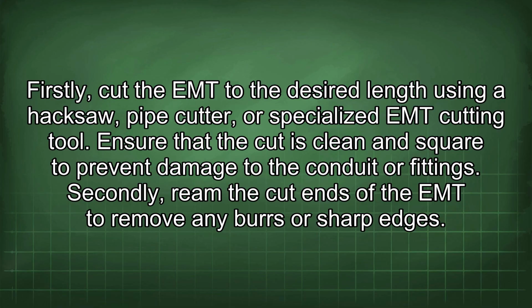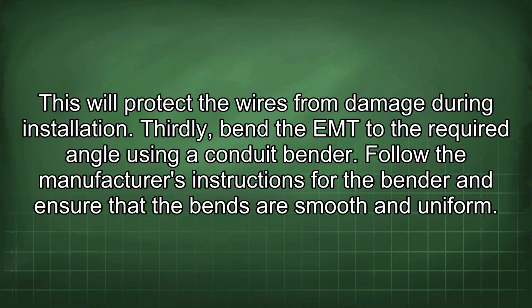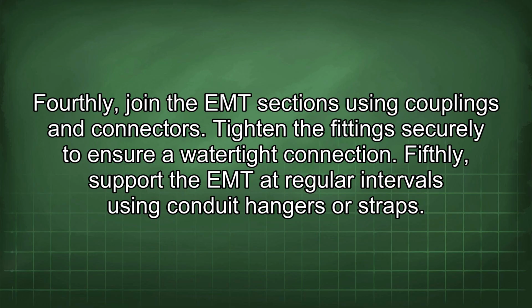Ensure that the cut is clean and square to prevent damage to the conduit or fittings. Secondly, ream the cut ends of the EMT to remove any burrs or sharp edges. This will protect the wires from damage during installation. Thirdly, bend the EMT to the required angle using a conduit bender. Follow the manufacturer's instructions for the bender and ensure that the bends are smooth and uniform. Fourthly, join the EMT sections using couplings and connectors. Tighten the fittings securely to ensure a watertight connection.